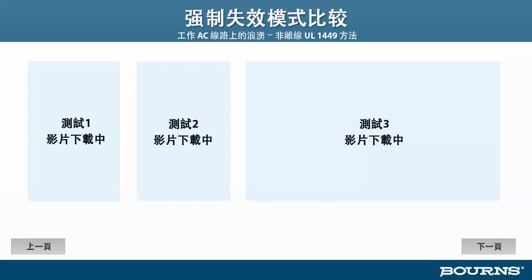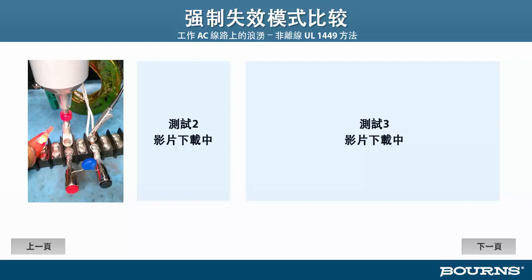The blue part is a 14mm class MOV. This is a quality conventional MOV design from a well-known manufacturer. We're applying its specified rated voltage, and we're going to apply its rated nominal 3000 amp surge. So in the lab, we would do this over and over again until we saw something happen. In this case, the device fails on the 11th surge. It did blow the 10 amp fuse, but this is not necessarily an unsafe failure. As you watch the video, you can draw your own conclusions.